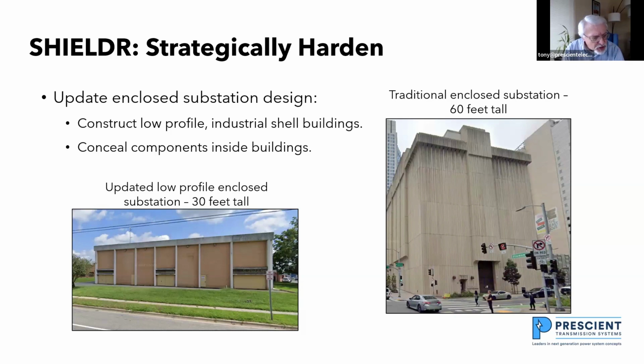I think we should be constructing low profile industrial shell buildings like the one on the left, built to match whatever's in the area. Our substations don't have to be more than 30 feet tall; they're so tall today because we're putting gantry cranes in them. With all skid mounted equipment, we can easily conceal components inside buildings, and in major city areas, components could even be inside parking garages, with the first two levels as a substation and the upper levels for parking.